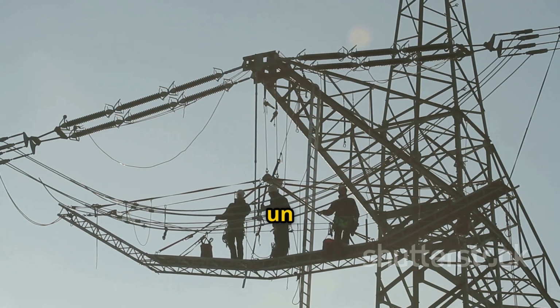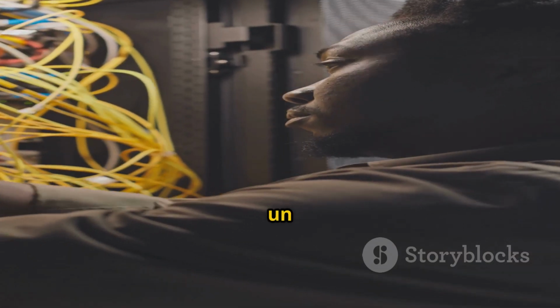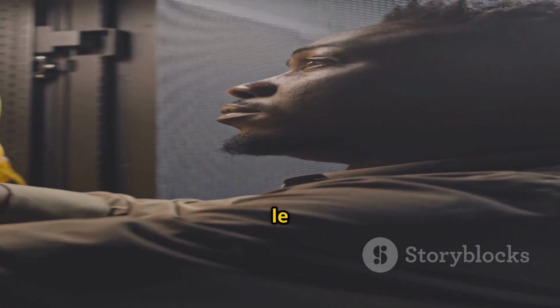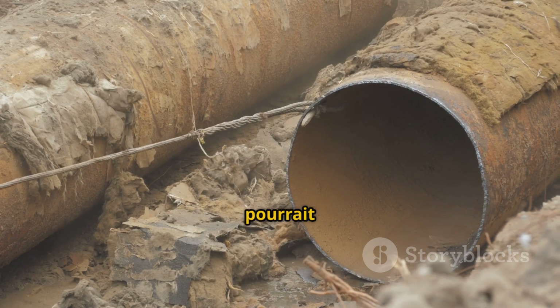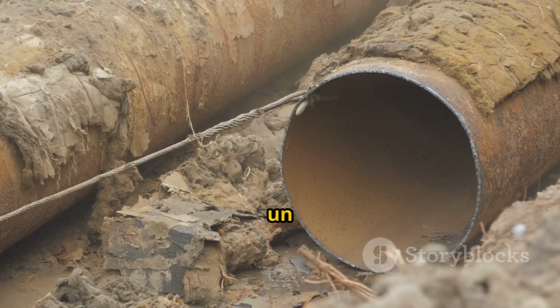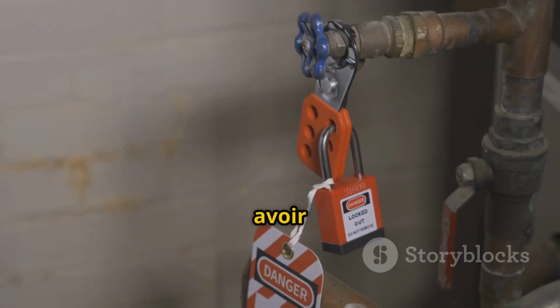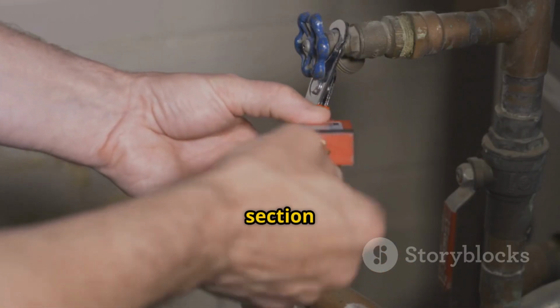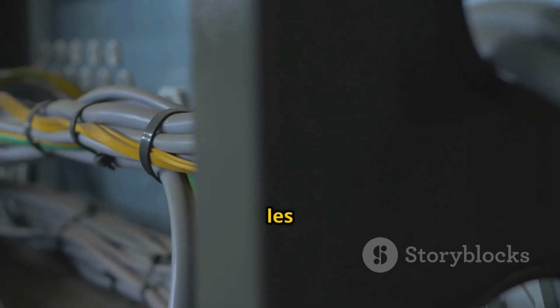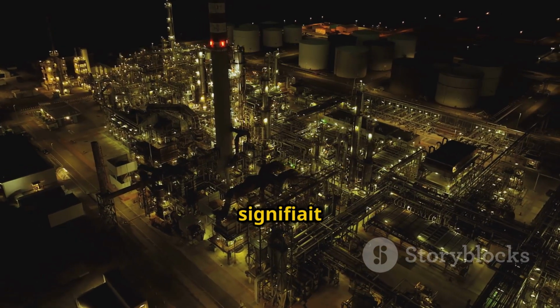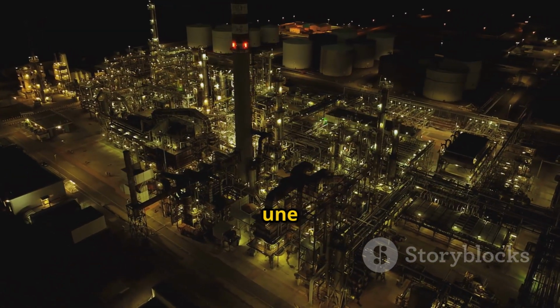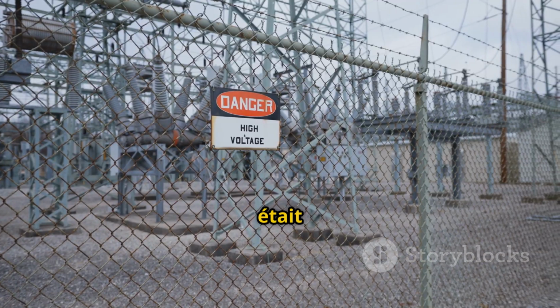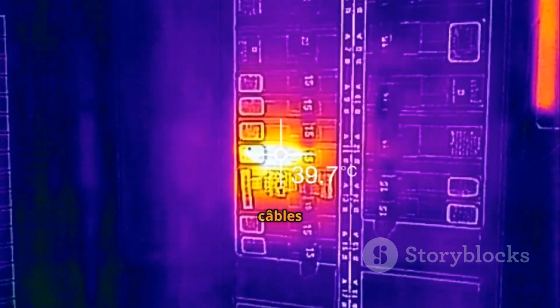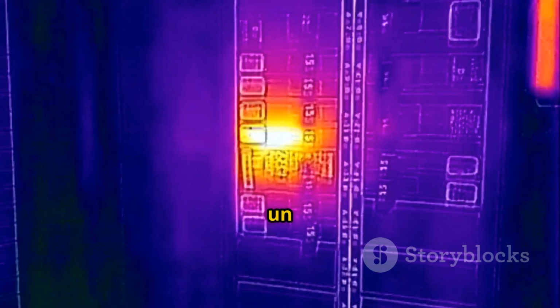Maintenance was a major issue. If one cable failed, finding and replacing it was monumental. Faulty wire might be bundled with dozens inside a sealed pipe. Electricians would have to de-energize a whole section, pull out all the cables, then feed them all back in. That meant extended downtime for a 24/7 facility. Safety was another concern. Heat from many power cables trapped in a sealed pipe created a fire hazard.